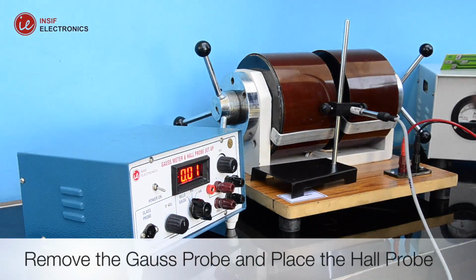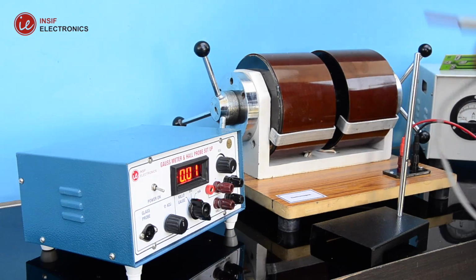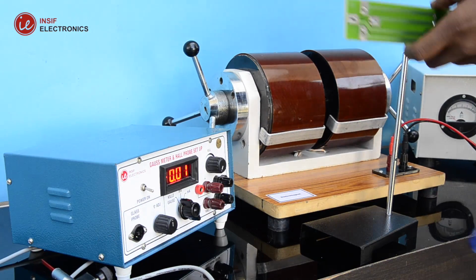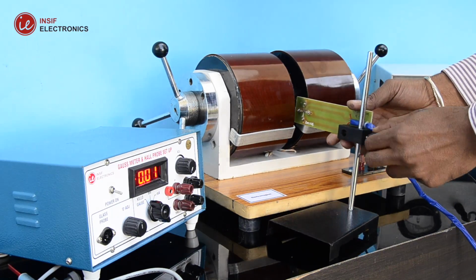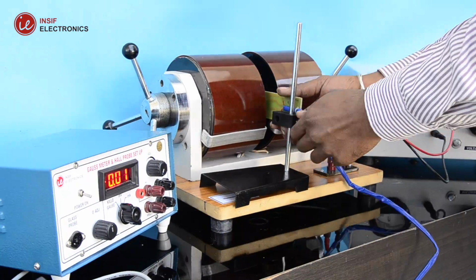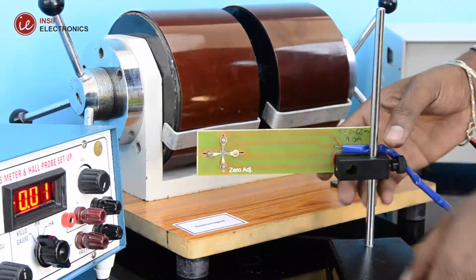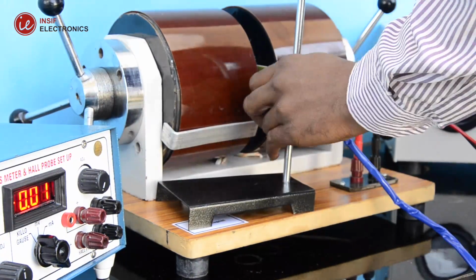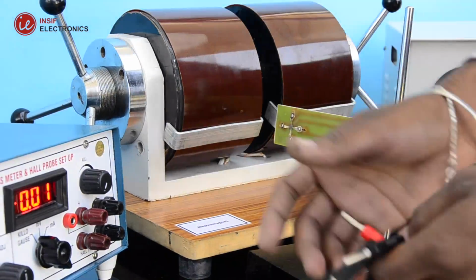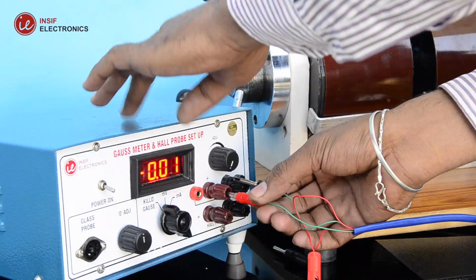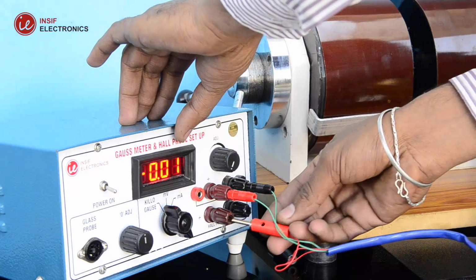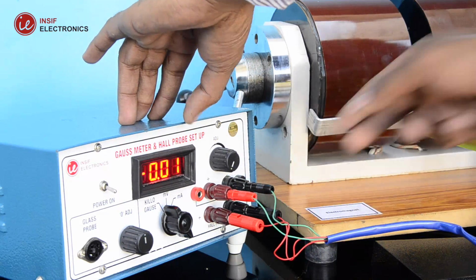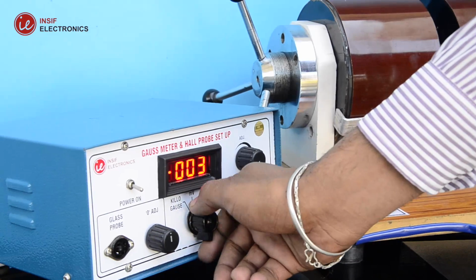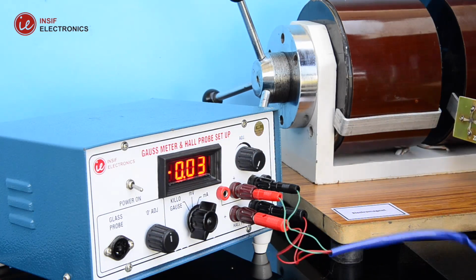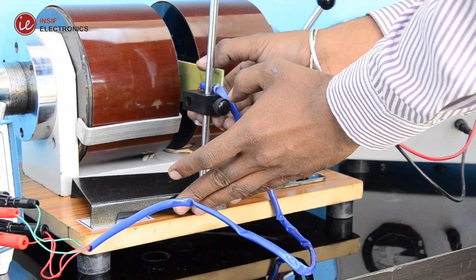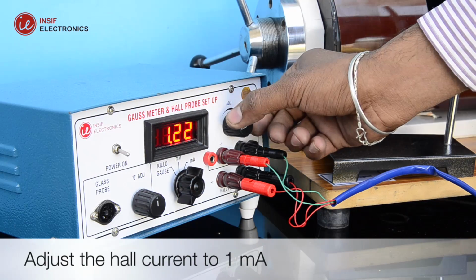Now remove the Gauss probe and place the Hall probe at the center of the electromagnet and then connect the probe as shown. Now rotate the knob to the milliampere position and adjust the Hall current to 1 milliampere.